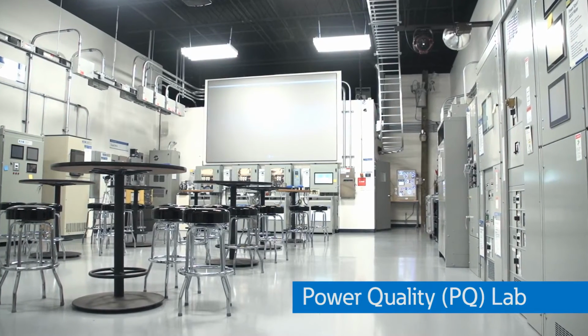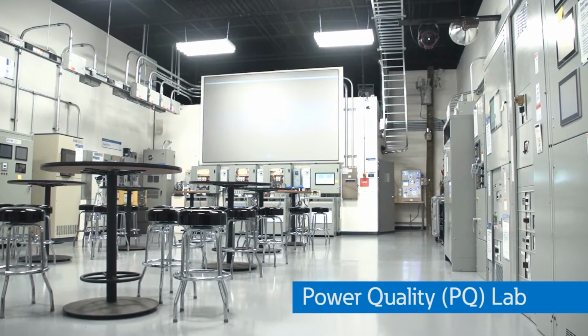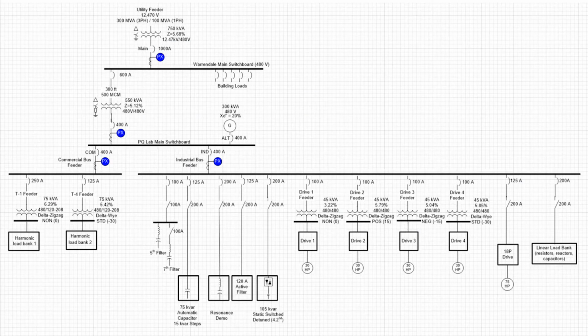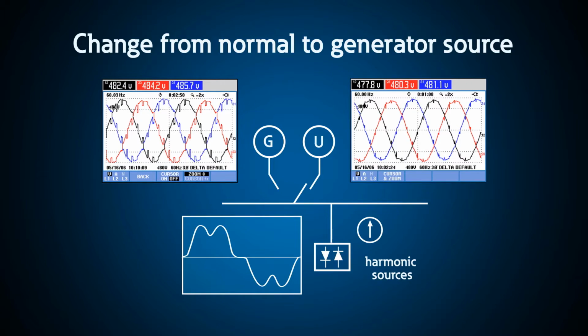The Power Quality Lab here at the PSEC is the perfect location for this resonance demo. All of the scenarios can be done with a significant amount of harmonic current generated by 6-pulse drives, as well as linear load from our customized load bank. In addition, we can show the effect of changing from a normal utility source to a high impedance generator source.